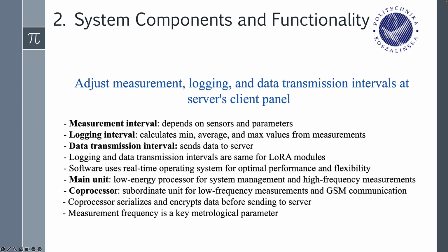The measurement, logging, and data transmission intervals can be adjusted to the customer's needs and set at the server's client panel. Measurement interval defines the frequency of receiving measurements from connected sensors. The value depends on the technical capabilities of individual sensors and the characteristics of physioclimate parameters. Logging interval defines the frequency of calculating received measurement data into minimum, average, and maximum values that have been aggregated in this period. Data transmission interval defines the frequency of sending recorded data to the server. The logging and data transmission intervals for measurement modules communicating via LoRa are the same.